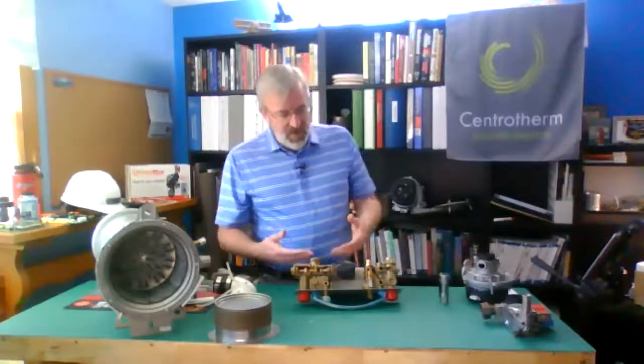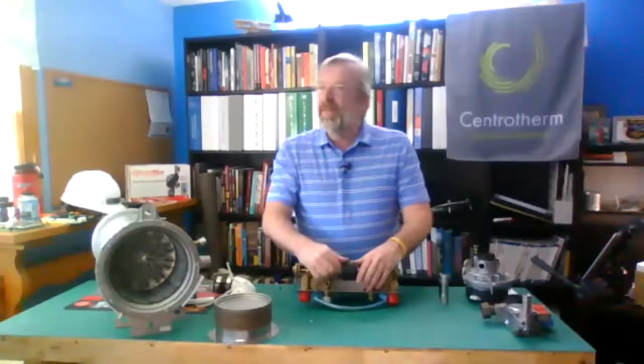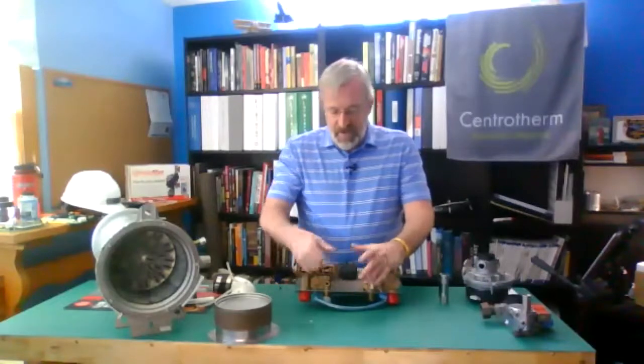What do we want to check here? Well, if you put a set of service valves on it and you want to clean it, flush the heat exchanger every service, certainly not a bad idea. It's not going to harm it, and that can be flushed just with any food grade type of acidic cleanser is what we're looking for. Get the lime and scale and any of that sort of stuff out there.